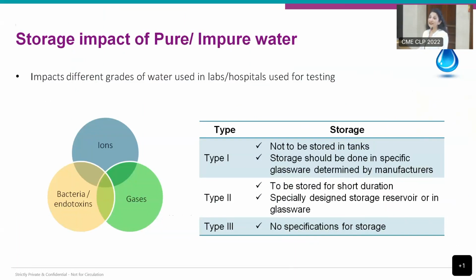Has anybody done that? हम लोग क्या करते हैं, can लेते हैं, we check the conductivity day one, maybe other lab will do pH, and we will put it to use. We will not even check next day or after that; we never recheck conductivity on a daily basis. Always keep in mind, when you have a can which is 20 liter and you are not able to consume it, you every day measure the conductivity and see, it will not last for more than 4 to 5 days. उसका conductivity बढ़ जाएगा. So never assume your conductivity is the same as you have estimated, right.